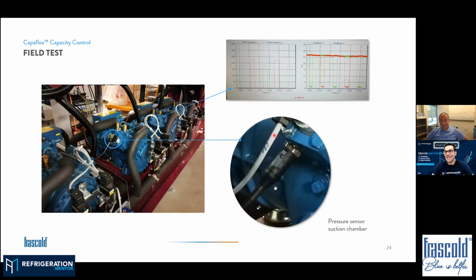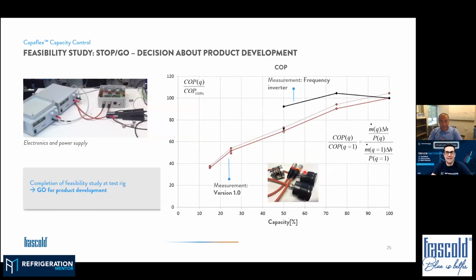Yeah, in order to have something that is reliable and efficient as well, because I showed you a graph, it has to be efficient in order to be interesting for the market as well. But here, just to show what we are saying, we had to equip all the compressors for the field test with high speed response pressure transducers in order to check that the sealing of that piston was still working, because we are talking about higher pressure difference again. So if one of those O-rings or parts is not sealing anymore, end of the game, we will not have the capacity control anymore. So this picture here is how the real system looks. When I was talking about the O-rings, these are the sealings.